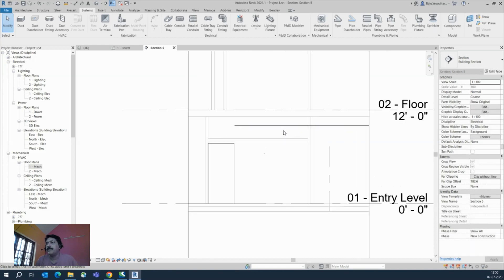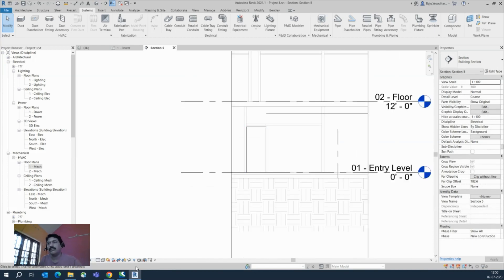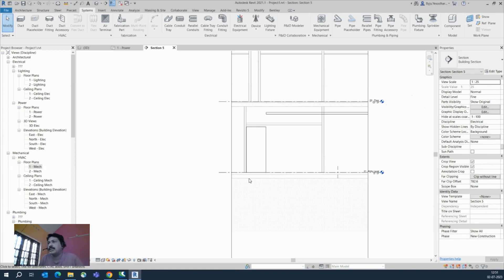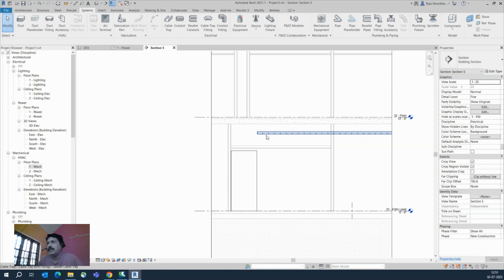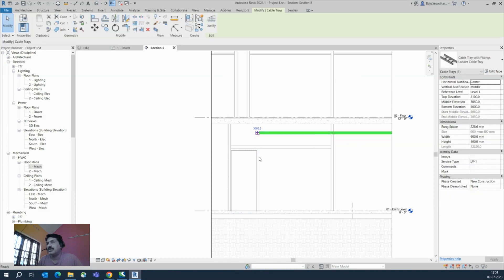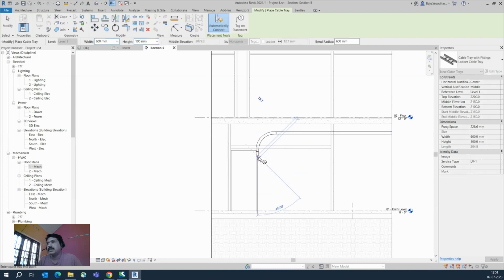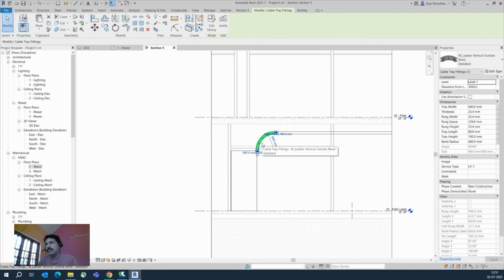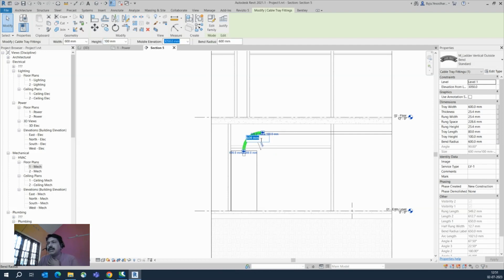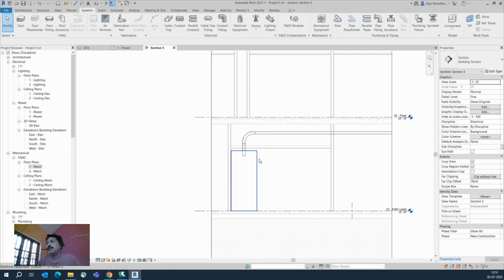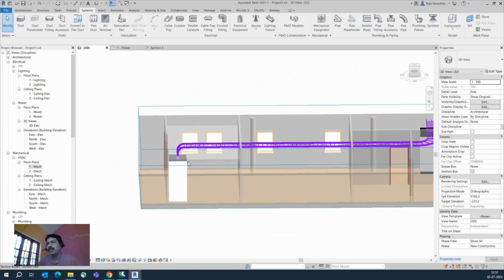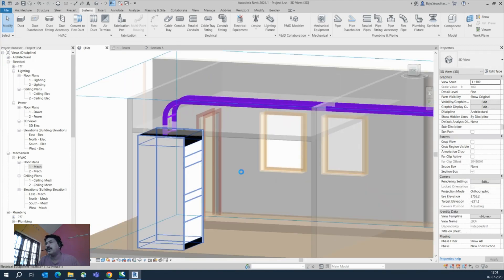In the section view you can adjust the cable tray — raise, lower, and position it. You can also change the scale, for example to 1:25. Right-click on the cable tray to make a bend. You can move it to align with the center of the panel. To change the bending radius of the cable tray, adjust it in the properties. The cable tray will automatically conform to the cable tray fitting.